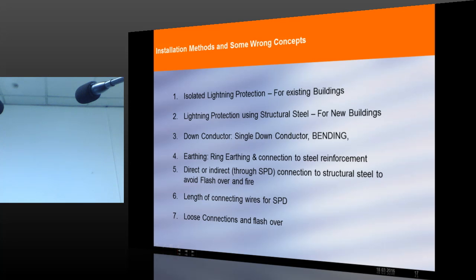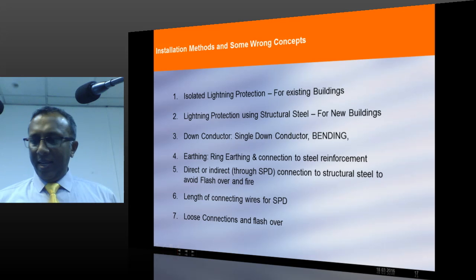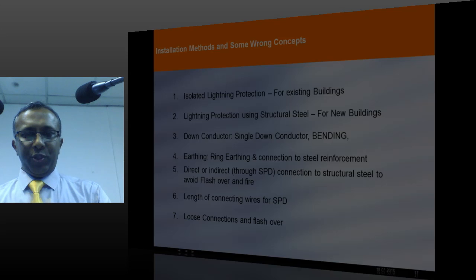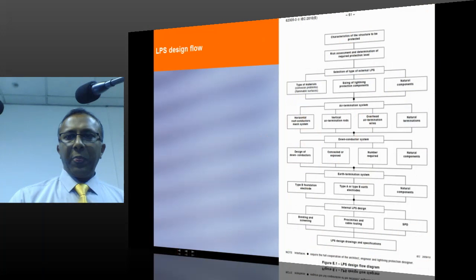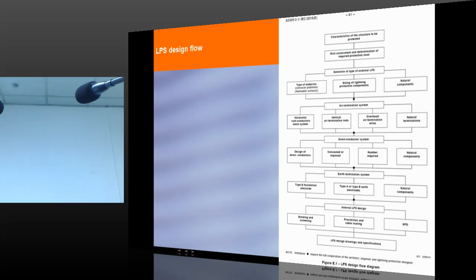But unfortunately, in several cases, SPDs are connected with long wires, which finally won't do the job, and loose connections and flash over. So here is the LPS, lightning protection system design, and this particular chart is from the standard. It explains how a lightning protection system needs to be designed. I won't go into detail because I think the printout is clear.